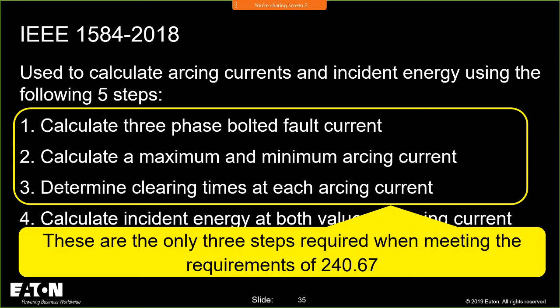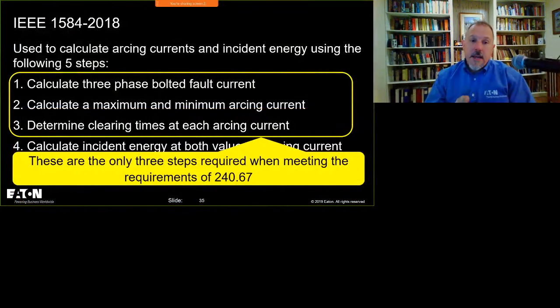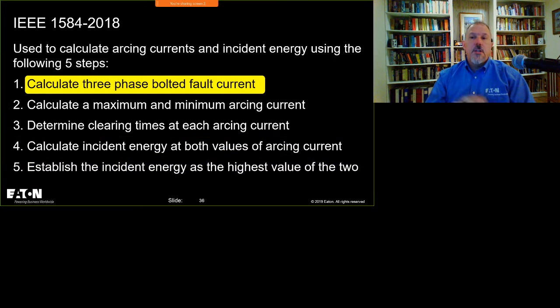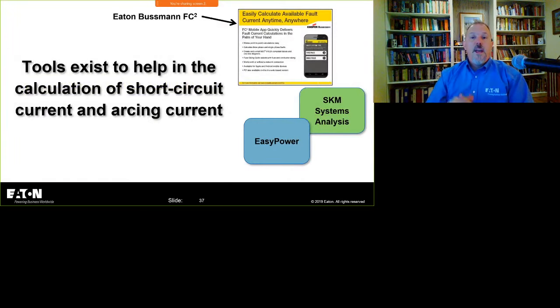We need to calculate that fault current, we need to calculate the maximum and minimum arcing current, and we have to determine the clearing times for both of those. So the tools we have for calculating the 3-phase bolted fault current, there are many. We have the Bussmann FC squared. Can you use that? Sure you can. It does give you a little bit conservatively high of a number, but you can still use that number.